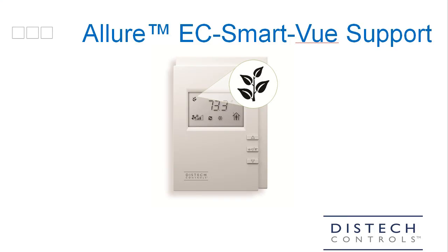Eclipse controllers now support the Allure EC Smart View series of communicating sensors through its subnet port. The connected system controller supports up to 12 Allure EC Smart View series communicating sensors, two of which can have a CO2 sensor. And the connected VAV controller supports up to four Allure EC Smart View sensors, two of which can have a CO2 sensor.